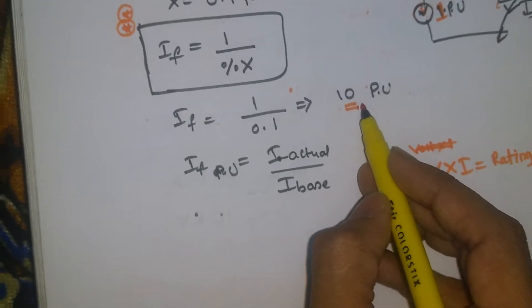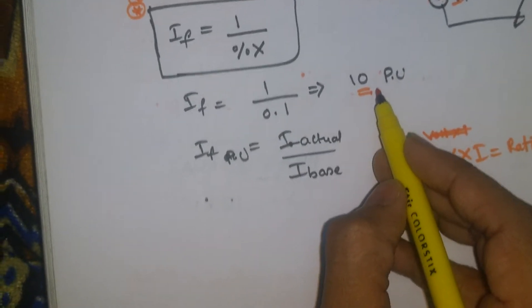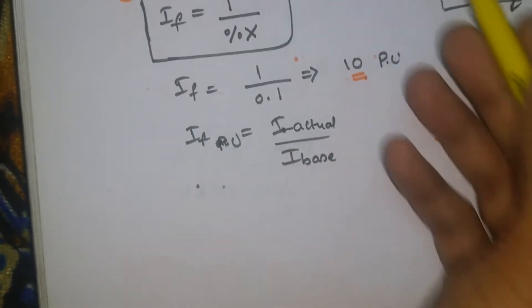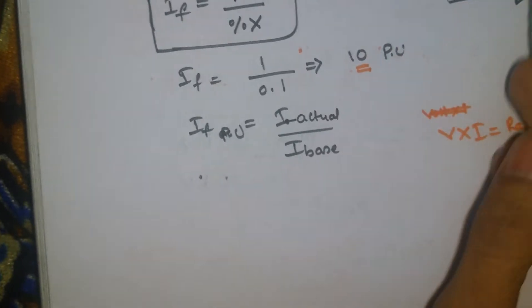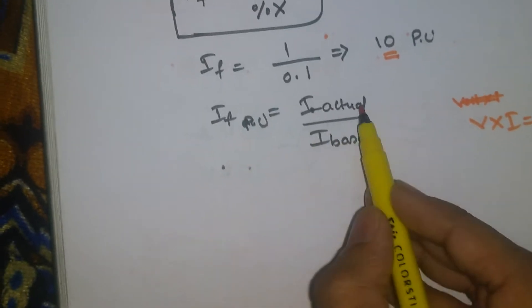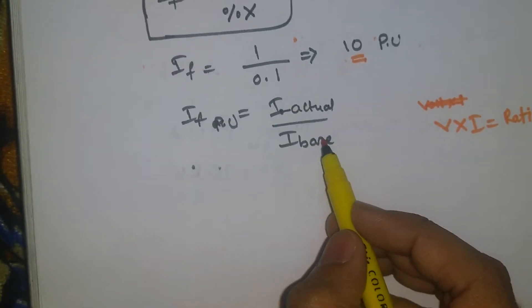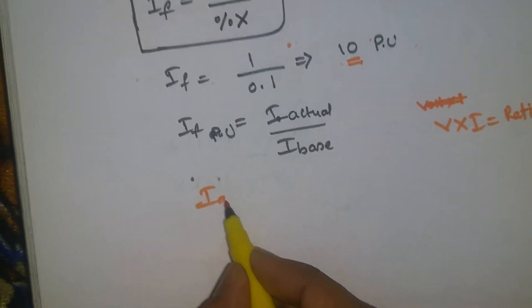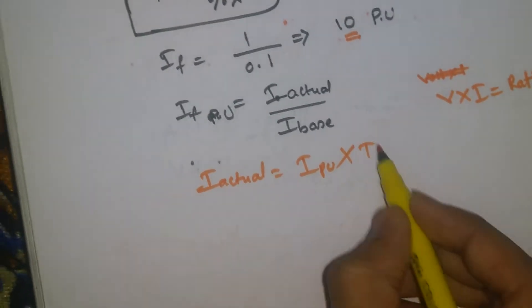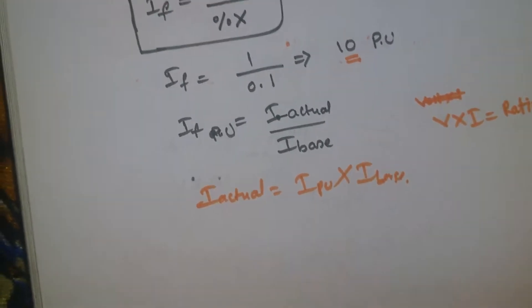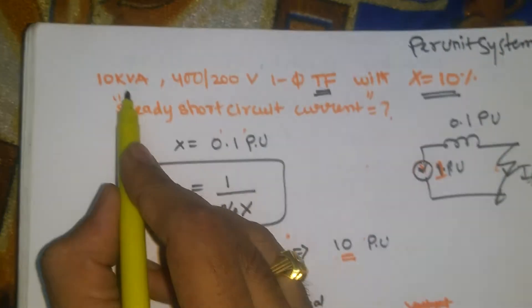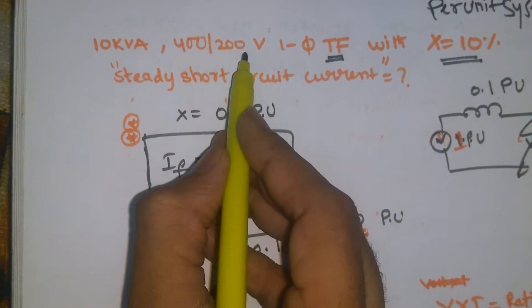We need to calculate the actual fault current or steady short circuit current. Per unit system is actual by base, so we want to find out the actual, but we have a per unit value. We need to find the base value. So where to find this base value? We have a rating, that is 10 kVA, 400 by 200 volts.